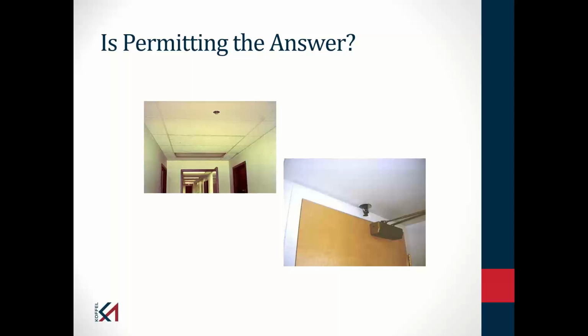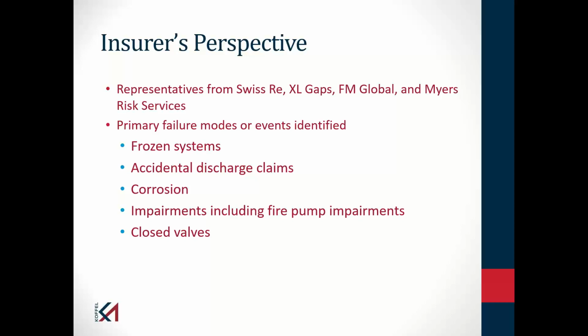If the spacing that I see here for these sprinklers was caused by some new construction activity, yes, I would expect that the building permit that you got for that construction activity would have identified that the sprinkler in the lower right-hand corner is too close and the sprinkler in the upper left-hand corner is too far away from the wall that we see. So during this workshop, we heard from the different interested parties or stakeholders. And the insurance industry, they said, we have reduced resources. We're not doing evaluations of buildings like we used to.